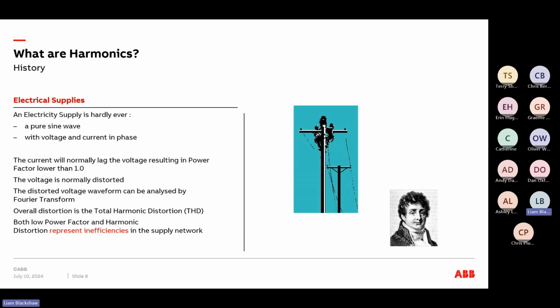You may have seen it as THDI, which means total harmonic current distortion, or we change that I to a V, and it just means we're looking at the total harmonic voltage distortion. But both low power factor and harmonic distortion represent inefficiencies in the supply network. In the next couple of slides there's a little bit of terminology that we'll go into, but I've hidden a lot of those slides because there's so much to talk about with harmonics. We could spend hours on this. So when you get a copy of the slide set, the hidden slides will be shown, so you can get an idea of the different bits of terminology, at least.